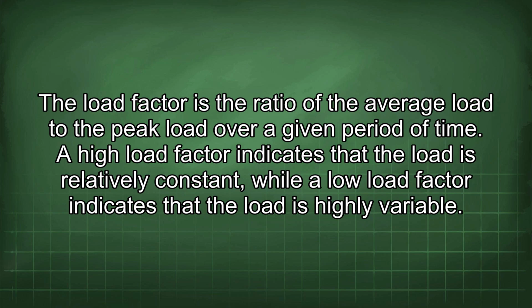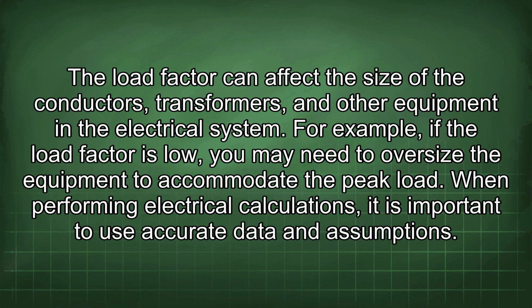A high load factor indicates that the load is relatively constant, while a low load factor indicates that the load is highly variable. The load factor can affect the size of conductors, transformers, and other equipment in the electrical system. For example, if the load factor is low, you may need to oversize the equipment to accommodate the peak load.